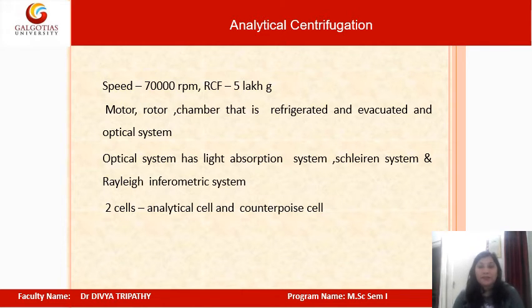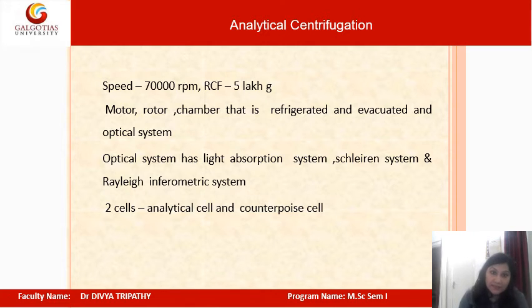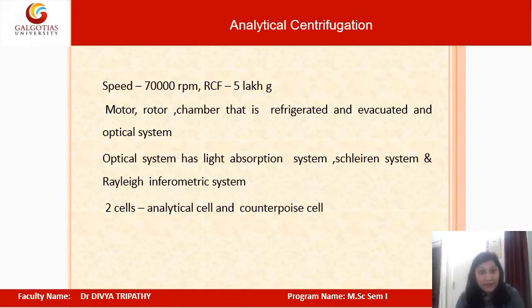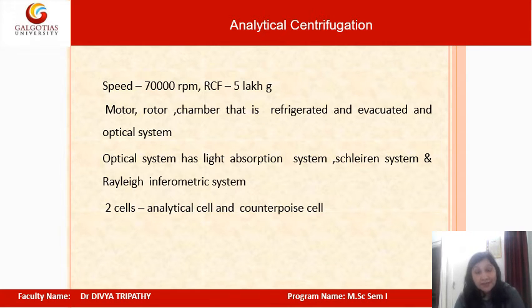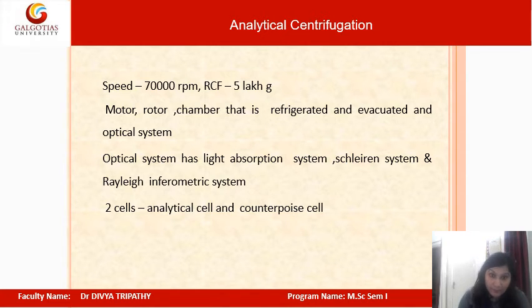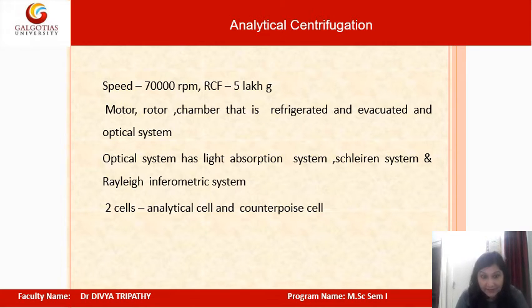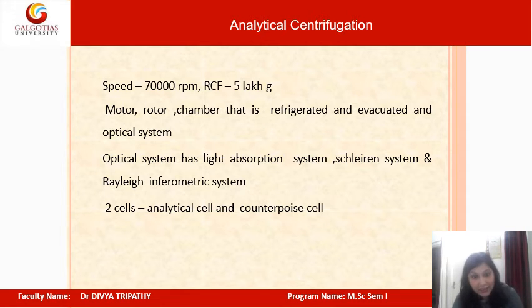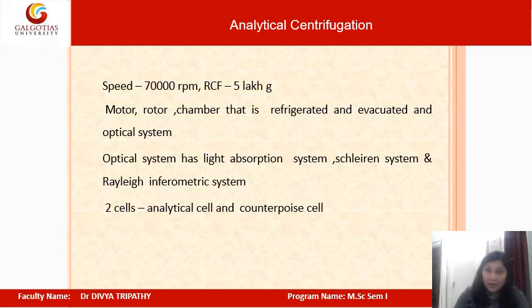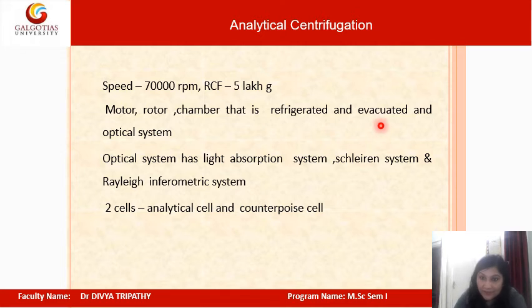Analytical centrifugation operates at 70,000 RPM with an RCF of 500,000 G. It has a motor, rotor, and a refrigerated and evacuated chamber. It is also mounted with an optical system comprising a light absorption system, a Schlieren system, and a Rayleigh interferometric system. It has two cells: an analytical cell and a counterbalance cell.